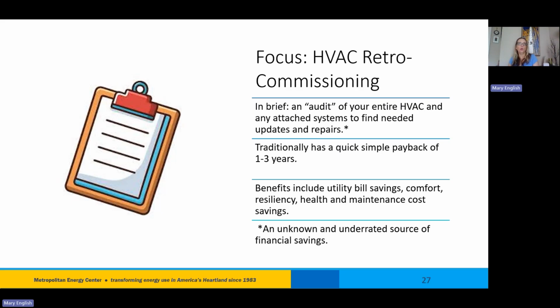Since this is an underused resource in our region, we don't have a ton of case studies on it, but I do have anecdotes. One professional gave a presentation saying he found over a third of the fan boxes in a VAV fan system he was retro-commissioning were not operating as designed—the fans weren't working. Had that commissioning not been done, it just would have been an uncomfortable, expensive office to run, because they wouldn't have had that information.